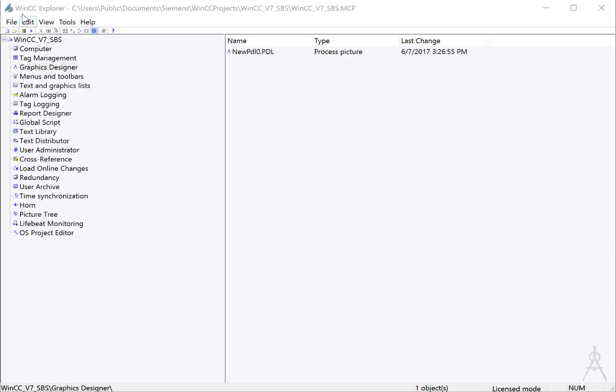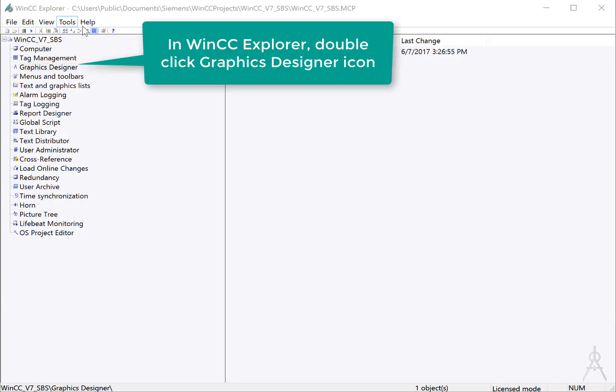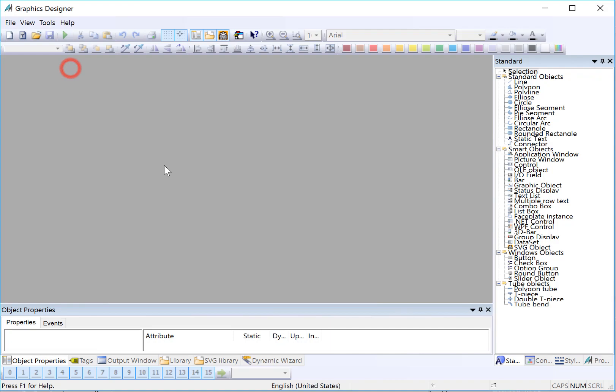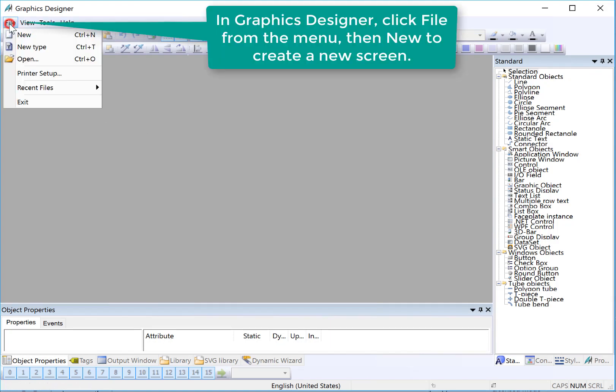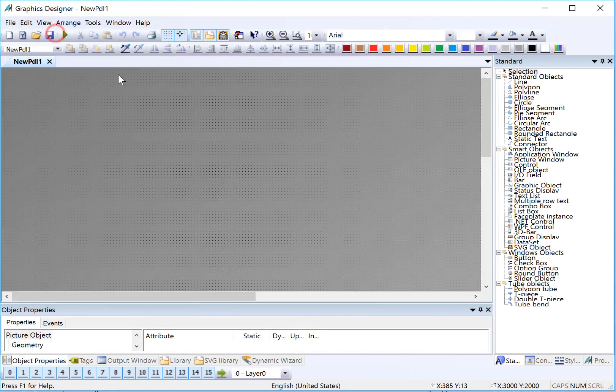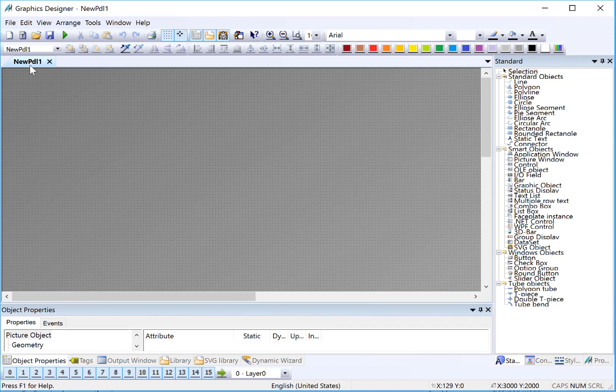We're going to begin in the WinCC Explorer. I'll highlight graphics designer and click to open. The graphics designer will open, and we're going to create a new screen. So I'll just do file, new, and it will open a new screen. Screens in WinCC are called PDLs, which stands for picture description language, so we use the term PDL and screen interchangeably.